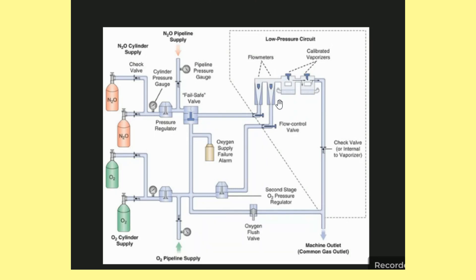When we use anesthesia drugs, we use the gas to vaporize the drugs. The vaporizer will mix the gas with the anesthetic agent and deliver it to the patient to keep the patient unconscious during surgery. The vaporized gases will mix and deliver to the patient, and the vaporizer is connected to the patient circuit.